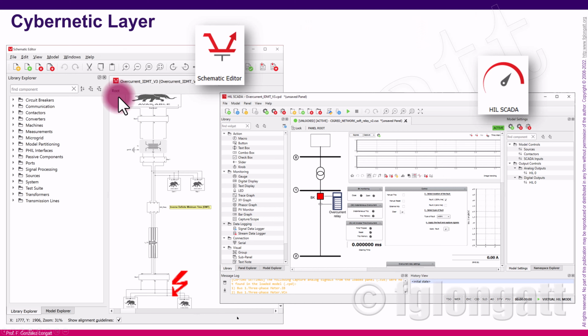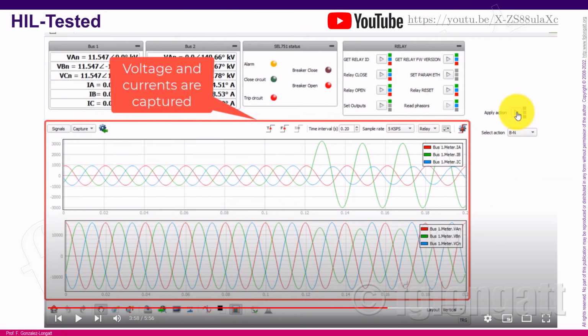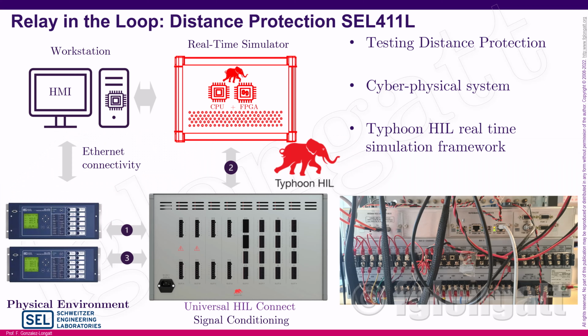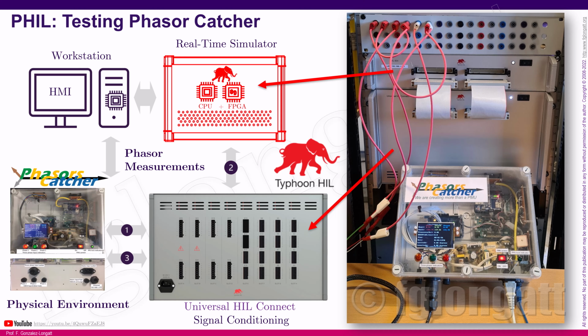When they apply the short circuit, the digital real-time simulator creates these signals in real time, and you can see the overcurrent applied to the relay in real time. You can also see the feedback coming from the relay showing the trip of the circuit and that the breaker is open. I'm running short on time, but there are some other examples here.